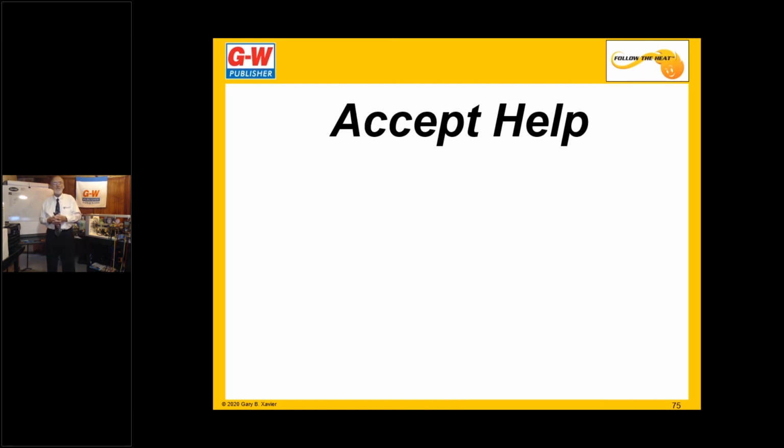And I called him up and I said, Randy, I need your help here. And he said, what do you got? And I said, well, this is what I told him. I think it's stuck in defrost. I advanced the defrost timer, and that seemed to solve the problem, but I just want it checked out. And he came and looked at it, and he said, you did exactly what I would have done. You advanced the defrost timer manually, what's it been doing since then? And I said, yeah, for the last couple of days, it seems to be working fine. And he said, that's what I would have done.